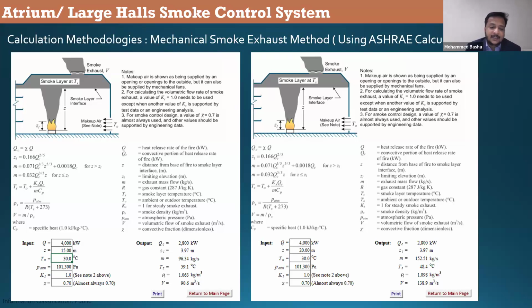So, for example, here the total volumetric flow rate required is 90.6 cubic meters per second. So approximately 90% of this shall be supplied through the makeup air. In some designs, you might not see the makeup air, and they will say makeup air is available within the room. No, that is not the case. Makeup air must be introduced because it helps buoyancy also.